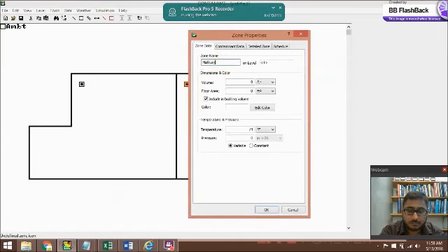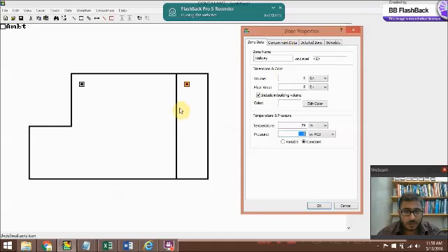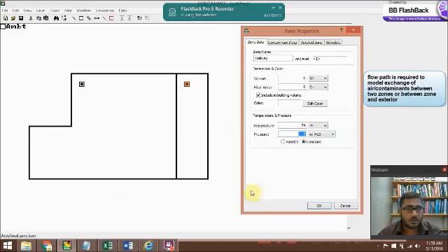And your temperature and your pressure difference. So suppose there's a hallway which is at a lower pressure and all your air is going in one direction, so you can determine it as a constant pressure, and that would determine your flow. This is one part to determine your flow. Your second would be to have a flow path, and that would determine your leakage area flow. This is like the zone pressure and temperature, which is usually variable.